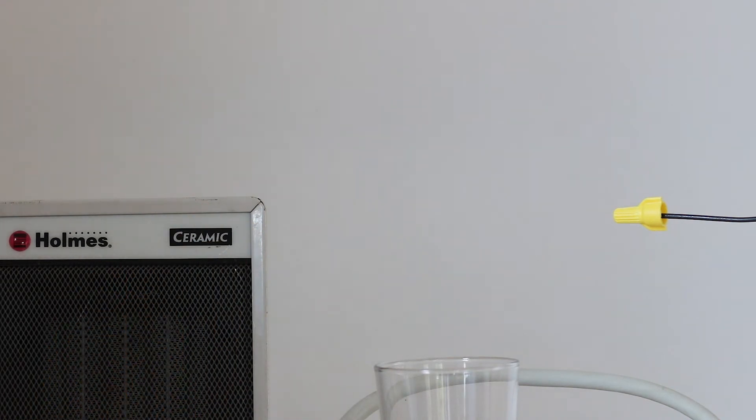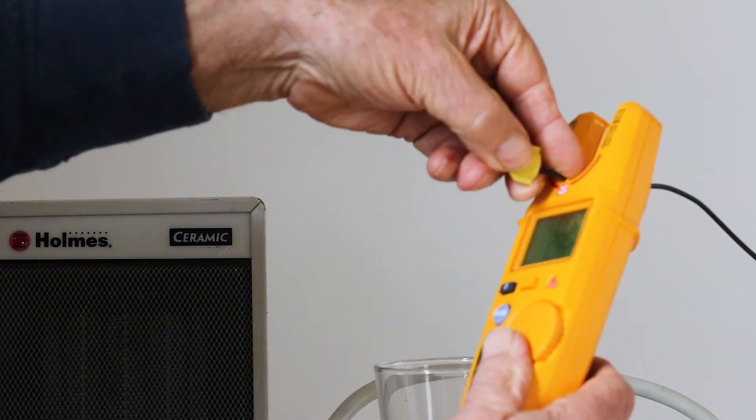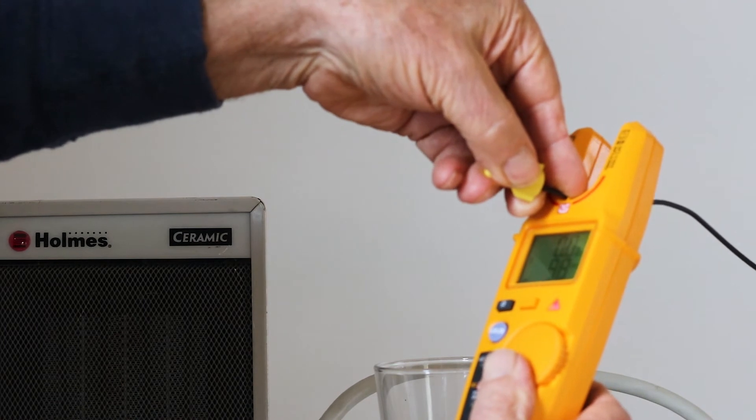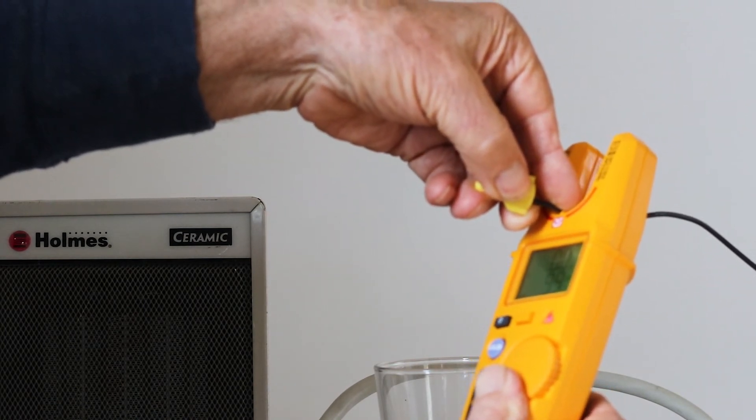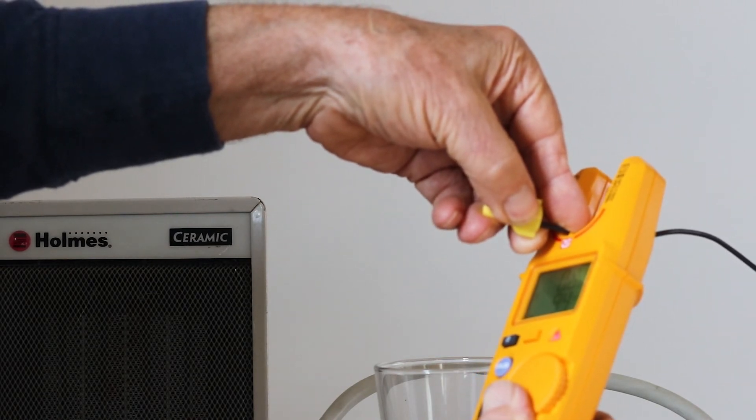An amazing thing about this meter is that the readout will become green when it is ready to measure. As you can see, I have a single wire energized from a 120 volt branch circuit. The readout has turned green, and it's right now reading 99 volts, which is about right considering all the wires it's going through.